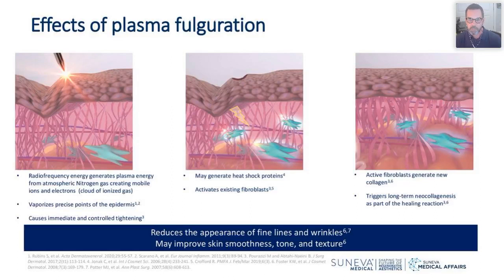In addition, because of the thermal heat that is generated, you end up with a thermal zone of coagulation. And if you're used to or understand many of the other types of technology that do heating, many of you are probably very familiar with Ulthera or micro-focused ultrasound, as well as radio frequency delivery. Each of those types of energy results in a superheating in a very focal way in the dermis. And it's that heating that activates the fibroblasts and other cells within the dermis to remodel the collagen. You also have a natural unwinding of the collagen, and that sets into place what I would term a basic thermal wound that will result in skin tightening because of the collagen unwinding and rewinding, as well as new collagen and elastin that are produced by those fibroblastic cells that have been activated due to the normal wound healing process.